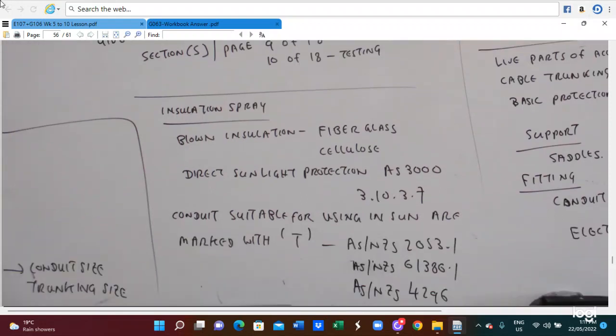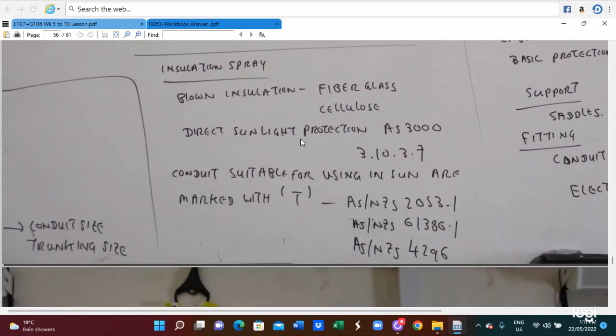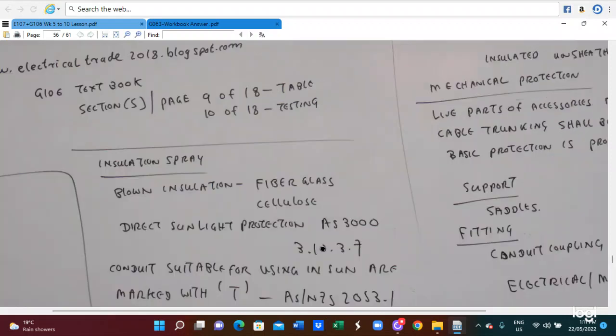And the next one, the insulations are separate. Blown insulation - fiberglass and cellulose. High sunlight protection: where to fall, utilize the standards of AS3000, clause 3.10.3.7. Conduit suitable for use in the sun is marked with the T, so that it follows AS/NZS 2053.1, AS/NZS 61386.1, AS/NZS 4296.